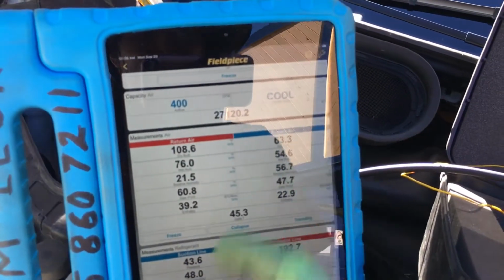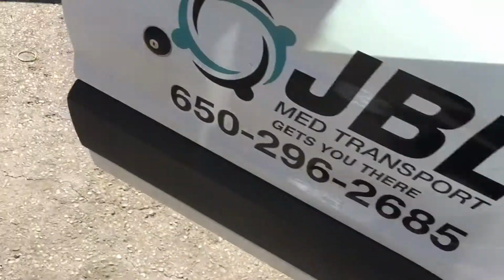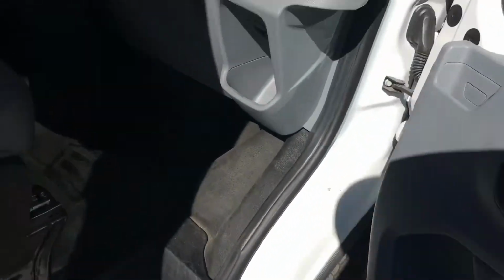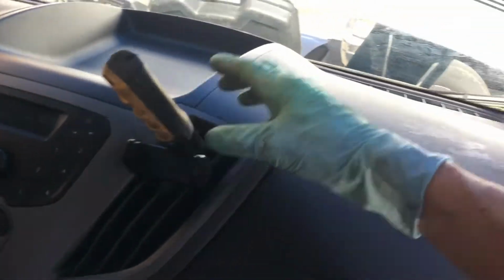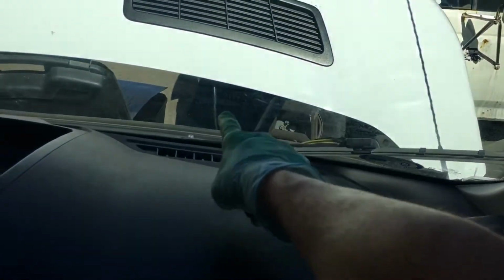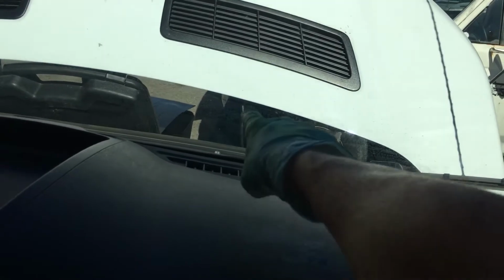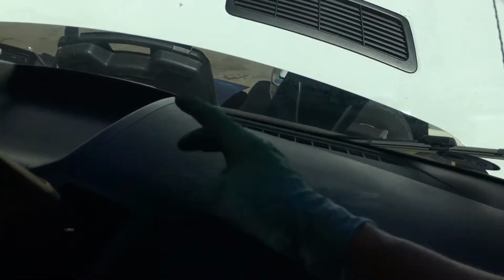And our outlet duct temperature is 63 degrees. That's coming out of the front. So we got 63, we got 115 degrees going in right where you see my temperature sensor probe right there. We got 115 degrees going in there, 63 degrees coming out of there. That's a pretty good temperature drop. That's what you would expect to see. Other than we don't have the heavy load going over the condenser. You put 115 degree in front of the condenser, it would get worse.